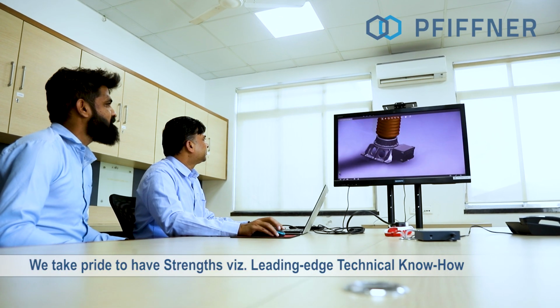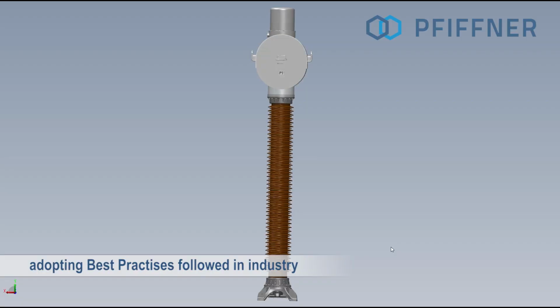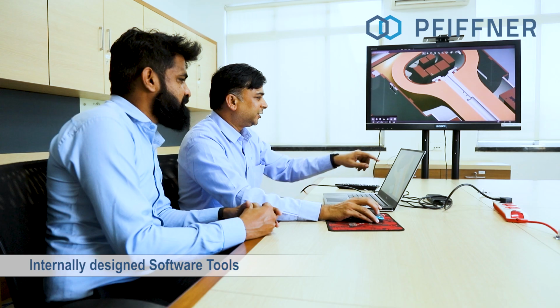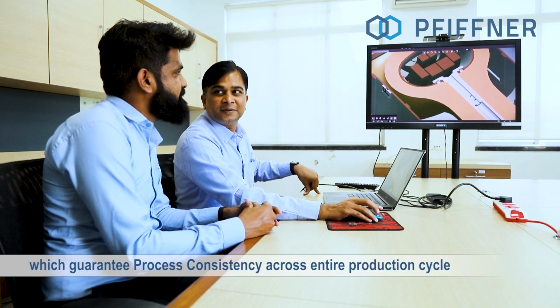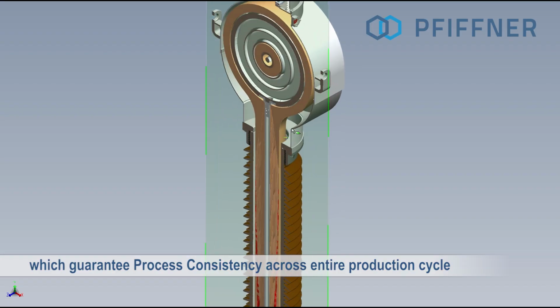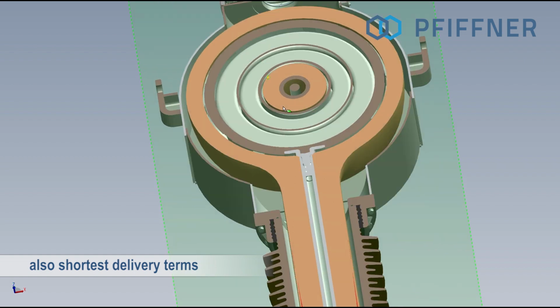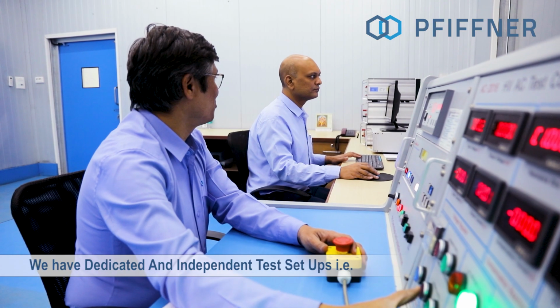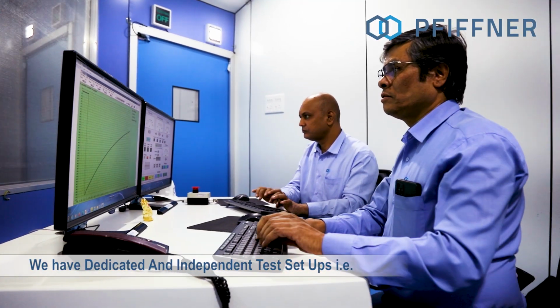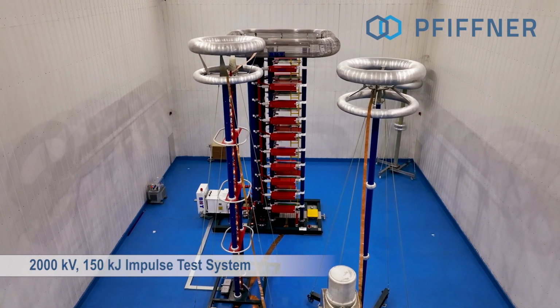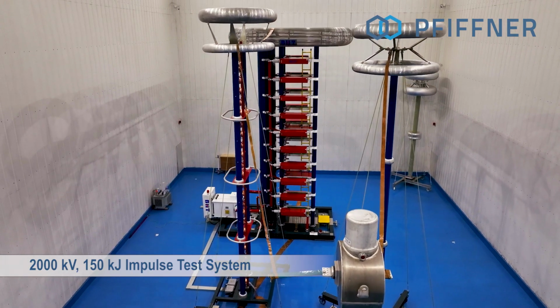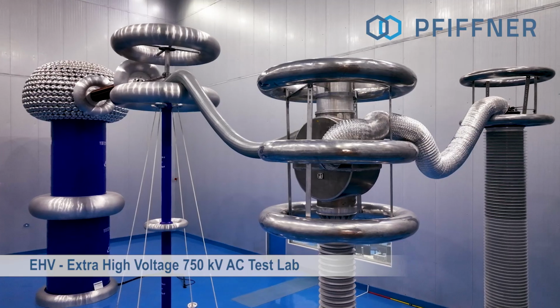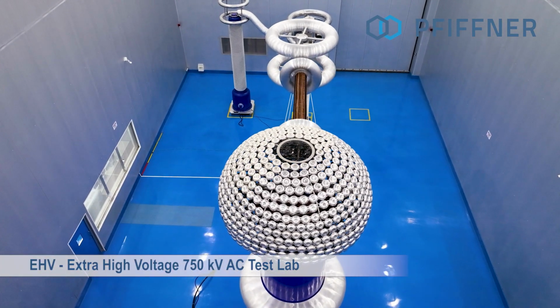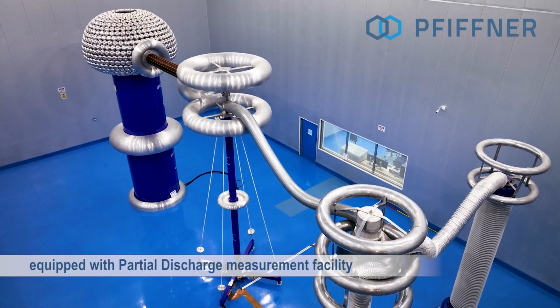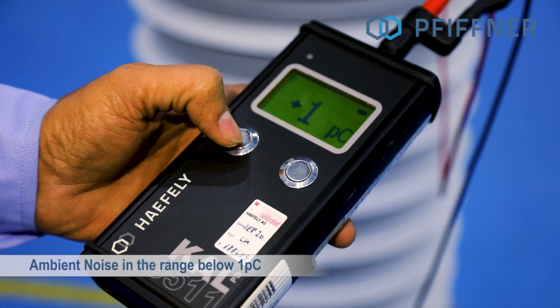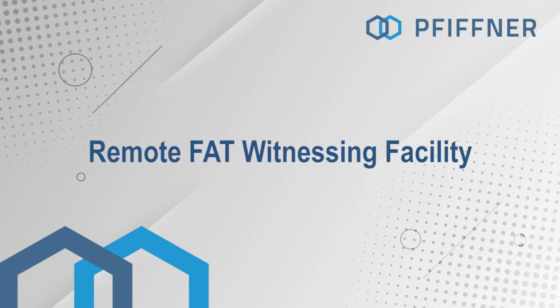We take pride in having strengths like leading-edge technical know-how, adopting best practices followed in industry, and internally designed software tools which guarantee process consistency across the entire production cycle and also the shortest delivery terms. State-of-the-art test systems: we have dedicated and independent test setups, that is, a 2000 kilovolt, 150 kilojoules impulse test system, and an EHV, extra high voltage, 750 kilovolt AC test lab equipped with partial discharge measurement facility with an ambient noise in the range below 1 pC, and a remote FAT witnessing facility.